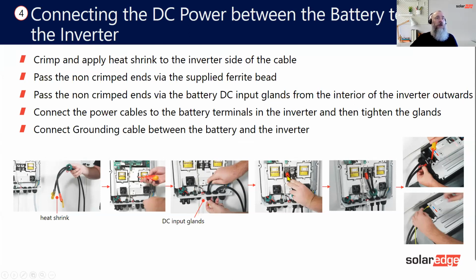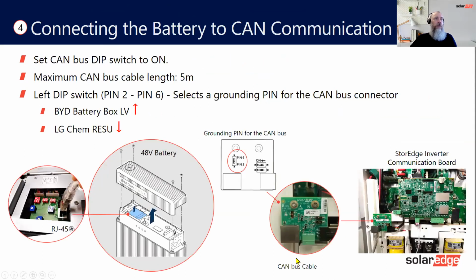So do it before and then pass the cables through. That's what we recommend. And you can see on here where they terminate. There's the ferrite bead there, as such, and there are the 2 holes. So the last piece is the communication, and this is for the CAN bus, and this was the extra bit. This little bit here, which is on the inverter, is this bit here blown up, and you can see we've got some dip switches here and dip switches here. What you must do, there are 2 different manufacturers, BYD and LG, as you can see. BYD is a switch up, so this is this one here, BYD up, LG Chem down, and then these 2 on. So just be careful that you've got the dip switches right.